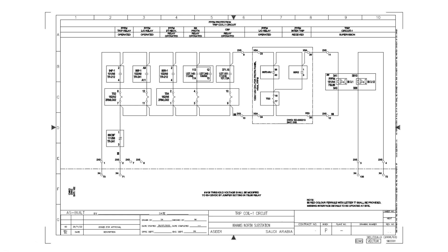In the case of circuit breaker failure, we have a dedicated Circuit Breaker Failure (CBF) relay for this CB. After 150 ms or 250 ms — whatever the setting — the CBF relay operates, and its contact, which is inserted in series with the tripping circuit, will get open. This blocks the positive continuously coming from 86F1 at that point; it will not reach the trip coil, and the trip coil will be safe. This is why we use the 86 CBF relay contact in series with the tripping circuit, and this scheme is called Save Trip Coil.